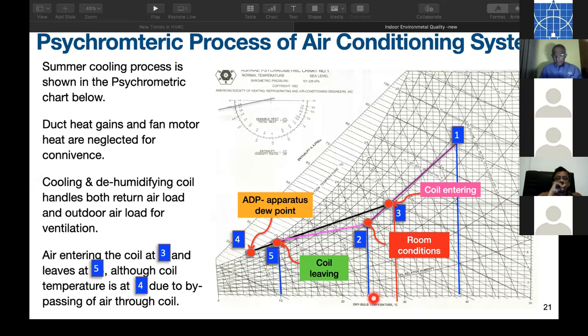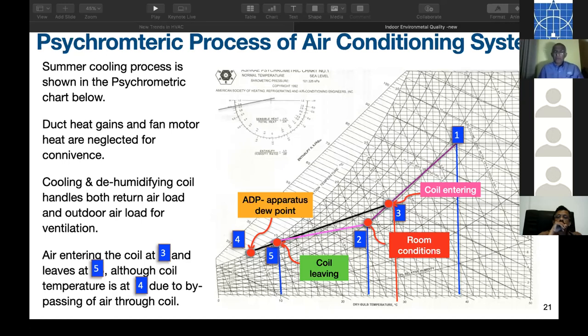Now, for instance, if the room is at 24, mixing may be 26, where outdoor in Sri Lankan condition is 32 C dry bulb. So entering at 26, it leaves at probably 12 degrees C, and then it undergoes another process, the room process, heating and humidification. I want to emphasize this simple air conditioning system comprises many psychrometric processes. One is air mixing, then cooling and dehumidification, then heating and humidification. Also, we have neglected heat losses and gains for our convenience.